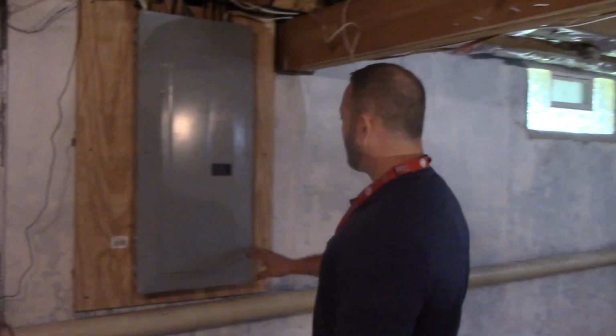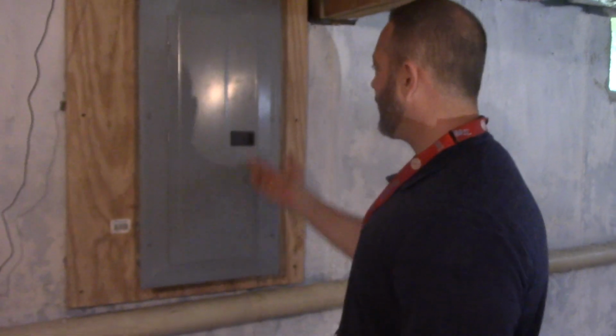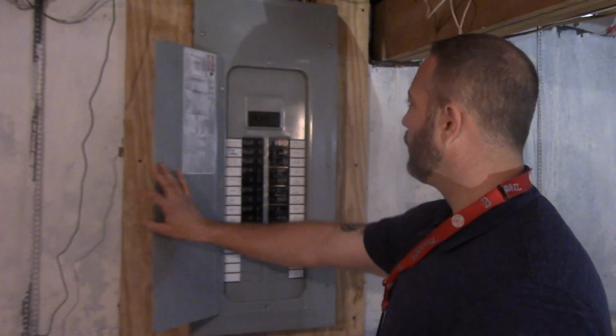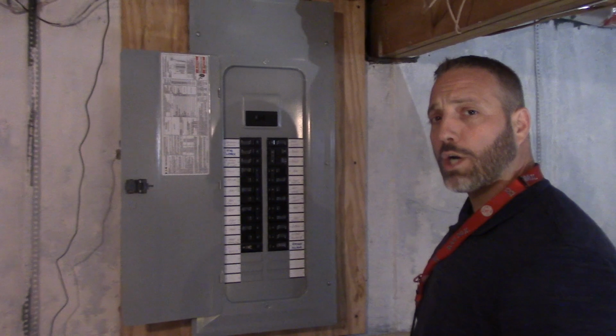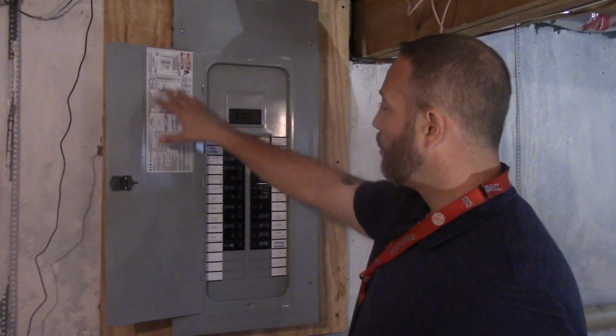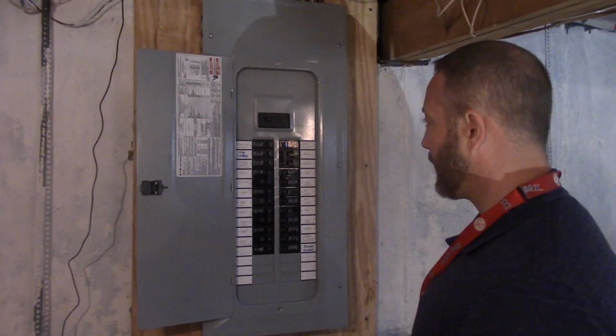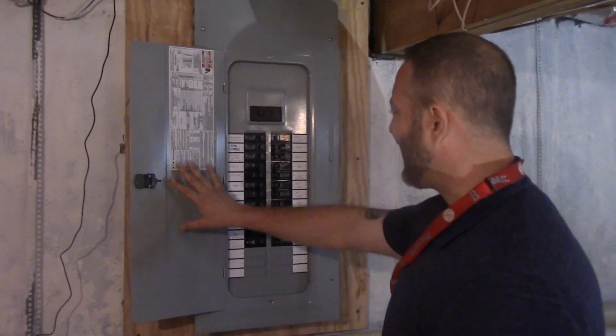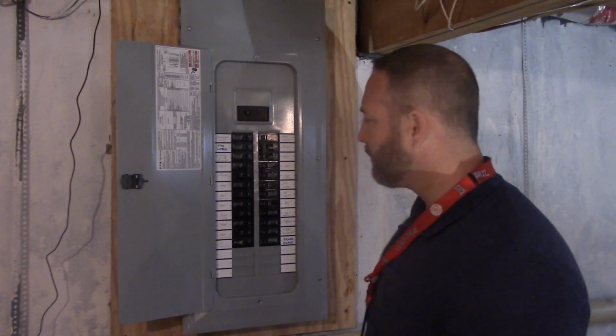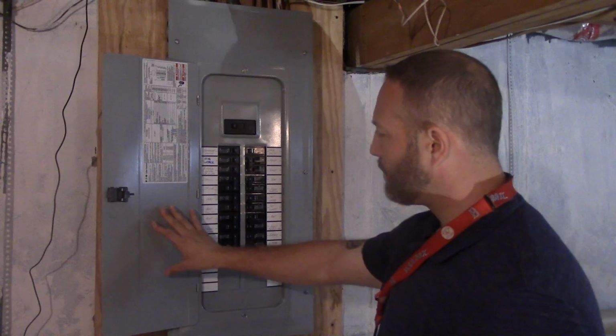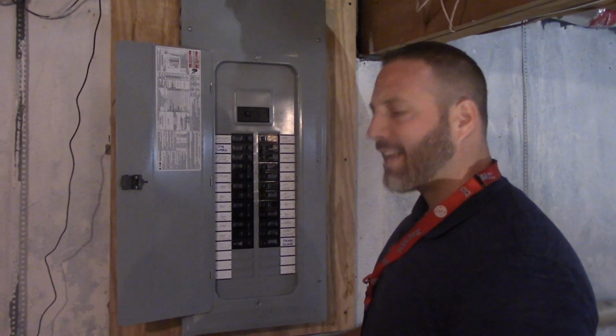So we're going to make sure that there are 6 screws on the panel. We're going to open up the panel. And there's a few things that we're just going to generally look at. One, we want to see if there is an inspection sticker on the panel. And I'm not seeing anything right now, so that's definitely a defect. All right, and that inspection sticker is by a third party.